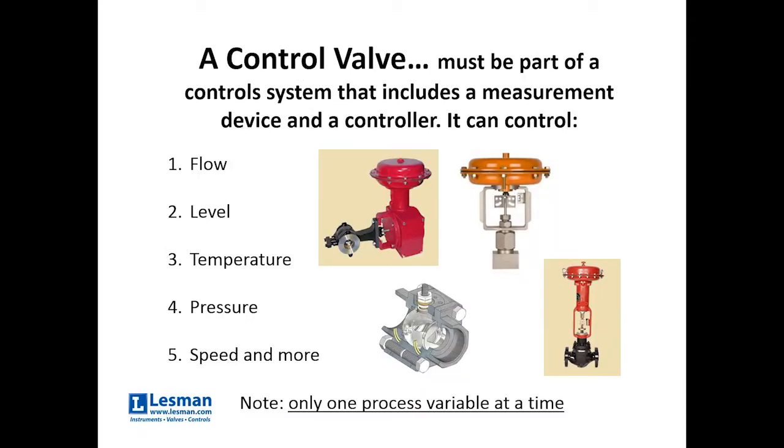So a control valve has to be part of a control system that includes a measurement device and a controller. And you can control all sorts of things with a valve: flow, level, temperature, pressure, speed of something that's run by air or steam as a motive force. There's lots of things you can do with a control valve. The most important thing is it can only do one at a time. It has to be a closed loop with a specific measuring device that's chasing one variable.